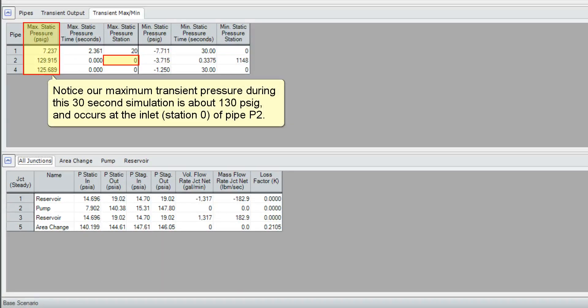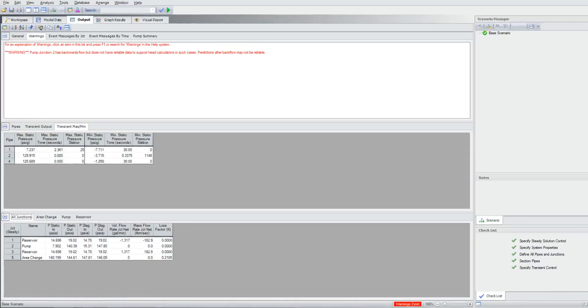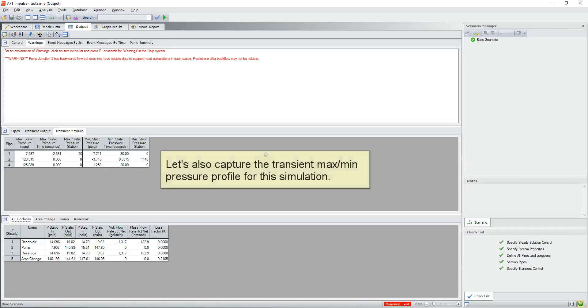Notice our maximum transient pressure during this 30-second simulation is about 130 PSIG and occurs at the inlet station zero of pipe P2.